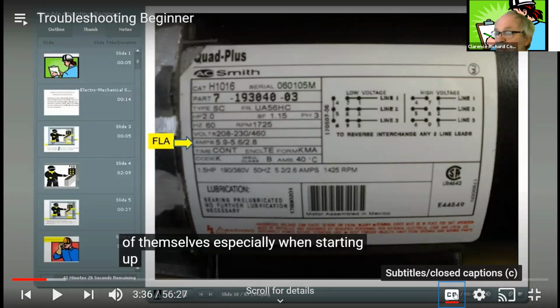High voltage, typically, you're going to take the 3 leads coming from your starter, and you're going to have 1 lead going to wire number 1 in the motor head there, and then another lead going to number 2, and number 3. Normally what I do when wiring them up is make sure they get good and taped up, and sometimes do that with high voltage tape. And then from that point, I tie 6 and 9 together, and 5 and 8 together, and 4 and 7 together. Make sure that those are tightly connected and tape them up appropriately. And now that's all set to go for 480 volts.